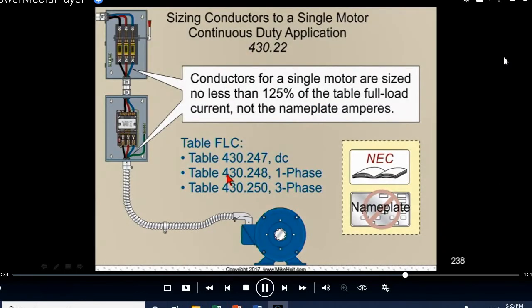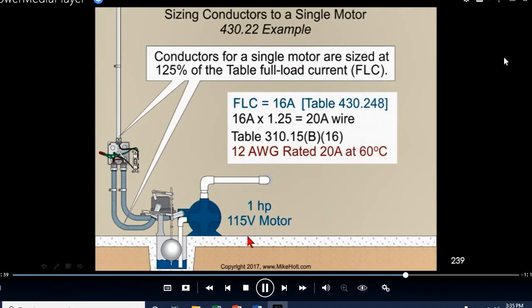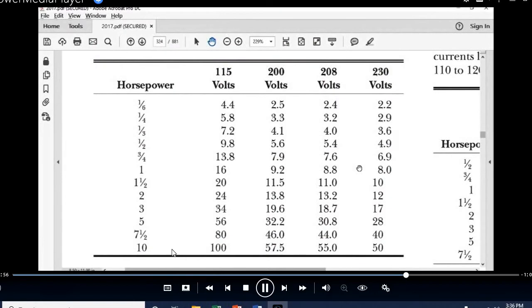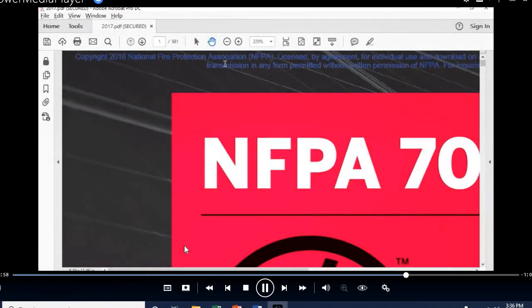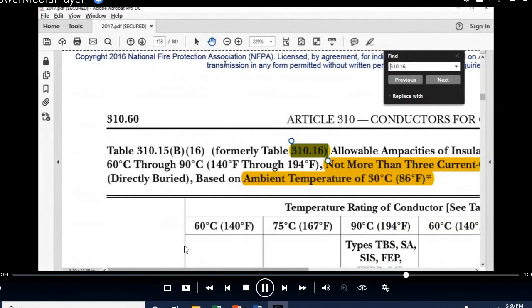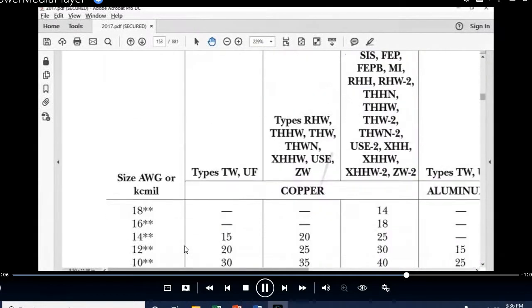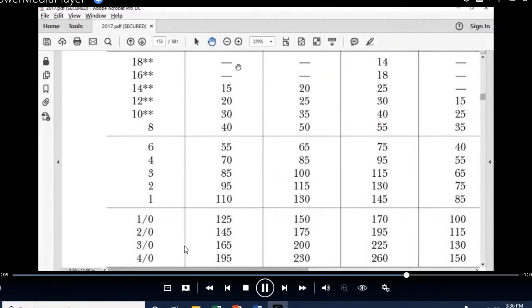And the rule was you size the conductor no less than 125% of the table current. The table current is 16 amperes. So then you take 125% of that. It comes out to be 20 ampere wire. And then you go to the code book, and we find out that 12 gauge wire at 60 degrees C is rated 20 amperes. So let's go to the code book. Let's go to 310.16, which is 310.15(B)(16). I go to the 60 degrees C column, which is the very first column here. I need a wire rated 20 amperes, and that would be 12 gauge wire.